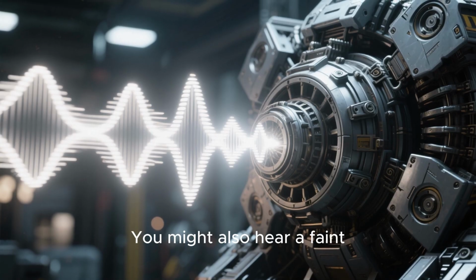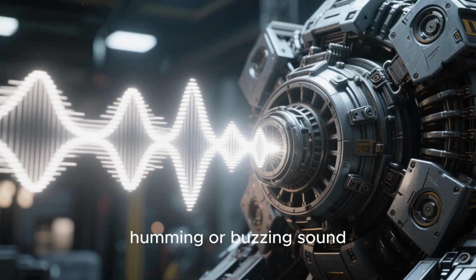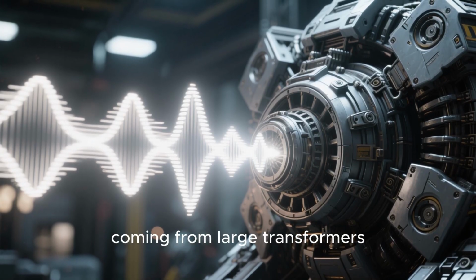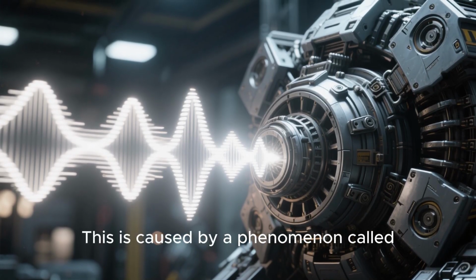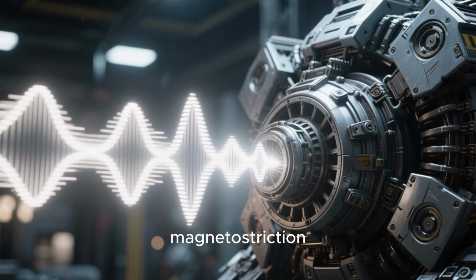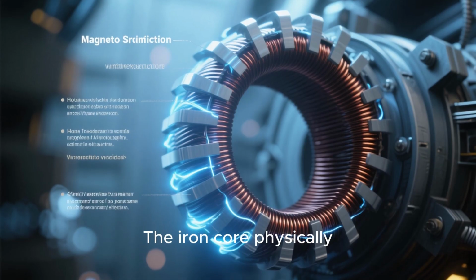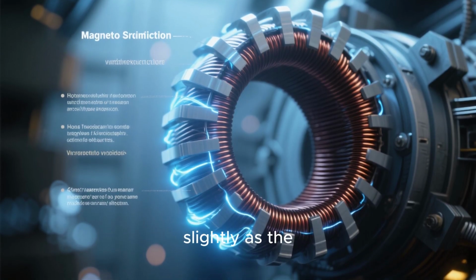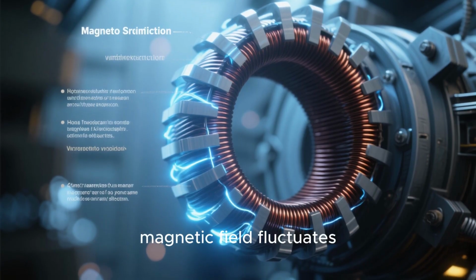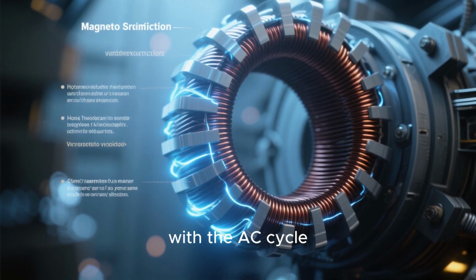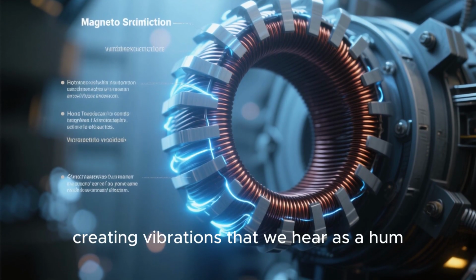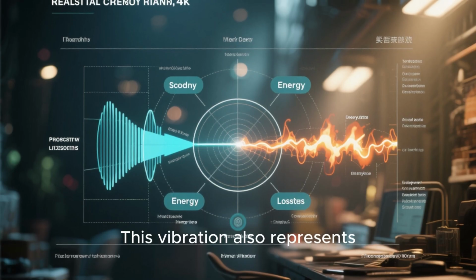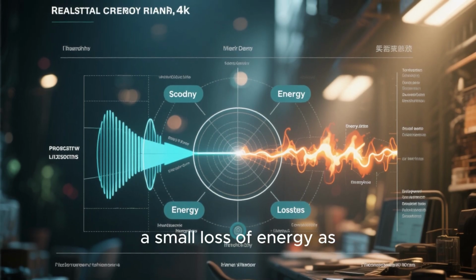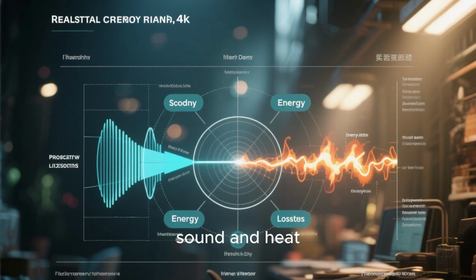You might also hear a faint humming or buzzing sound coming from large transformers. This is caused by a phenomenon called magnetostriction. The iron core physically expands and contracts slightly as the magnetic field fluctuates with the AC cycle, creating vibrations that we hear as a hum. This vibration also represents a small loss of energy as sound and heat.